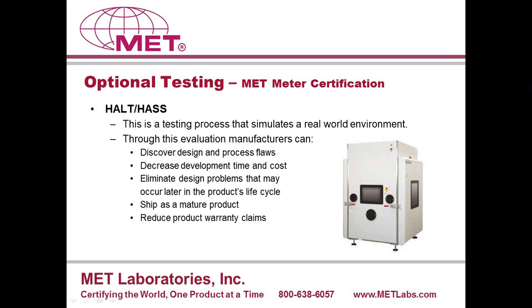That program is not going to assure you that this meter, for example, on the side of a home is going to be there for 15 or 20 years like the old electromechanicals were. But it will give you a high sense of assurance that it is a reliable product at the end of that program. Because you're really trying to break it, fix it, break it, fix it, to the point where it really comes out of that test program as a ruggedized product.